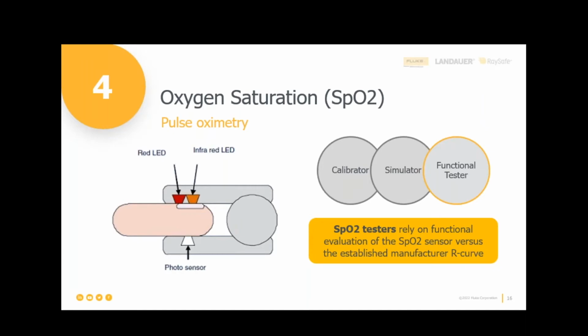Right, so when you're going to do the testing on this, you don't have human blood that's going to biochemically mimic what's going on with any other patient in the world. You don't have that. You have a functional tester that has got built into it one way or another, a way to interact with the oximeter and the patient monitor so that you get a specific reading based on the R curve of that brand and model of oximeter. Okay, because Spacelabs will be a different R curve than the Nellcor or the Masimo, and those are not the only oximeters in the world.